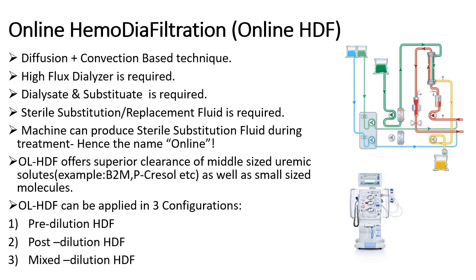Just like HF, haemodiafiltration can also offer superior higher molecular weight clearance as well as small molecular weight clearance, such as beta-2 microglobulin, urea, and creatinine, because both solute transport mechanisms are involved. Diffusion is used for the removal of small molecules and convection for the removal of medium to large sized molecules, resulting in superior clearance of both.